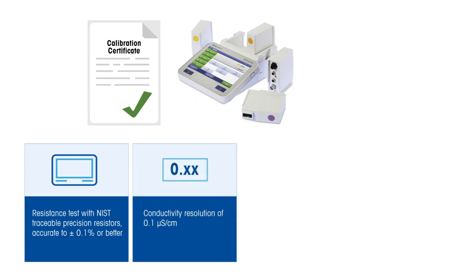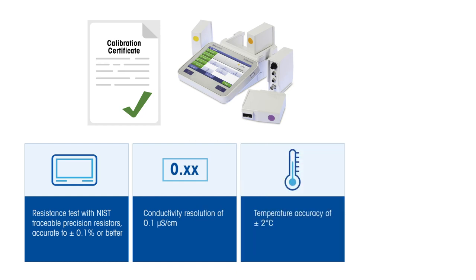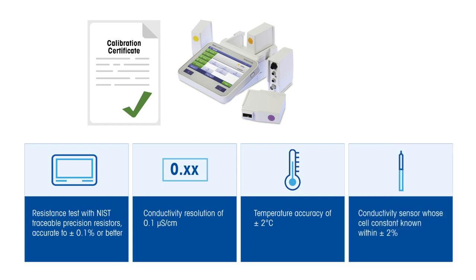Additionally, the measurement system should have a conductivity resolution of 0.1 microsiemens per centimeter or better, and a temperature accuracy of plus or minus 2 degrees Celsius. The conductivity sensor used must have a cell constant known within plus or minus 2%.